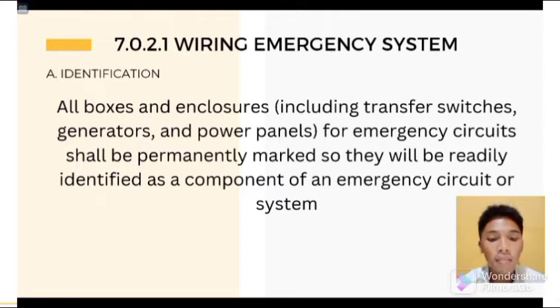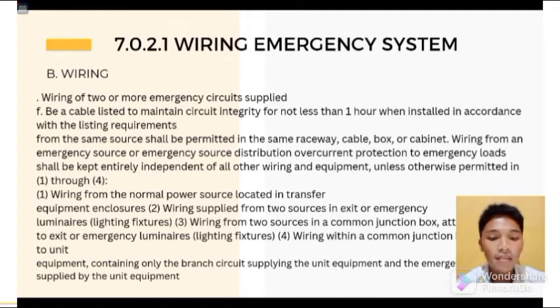Wiring from an emergency source or emergency source distribution overcurrent protection to emergency loads shall be kept entirely independent of all other wiring and equipment, unless otherwise permitted in number 1 through number 4. So here are those. Number 1, wiring from the normal power source located in transfer equipment enclosures. 2, wiring supplied from two sources in exit or emergency luminaires. 3, wiring from two sources in a common junction box attached to exit or emergency luminaires. Number 4, wiring within a common junction box attached to unit equipment containing only the branch circuit supplying the unit equipment and the emergency circuit supplied by the unit equipment.